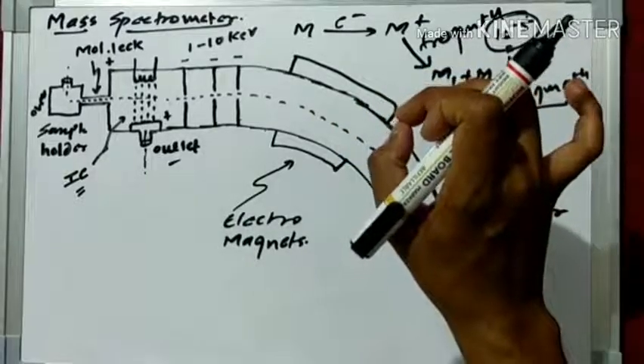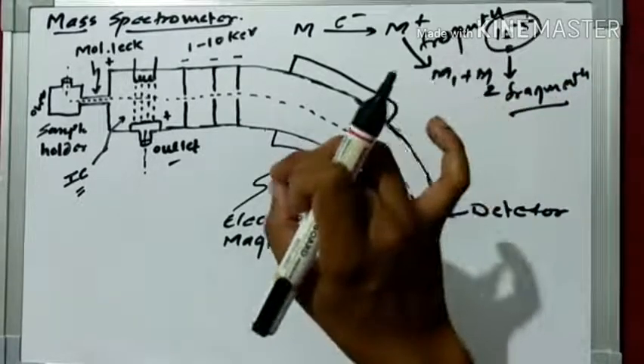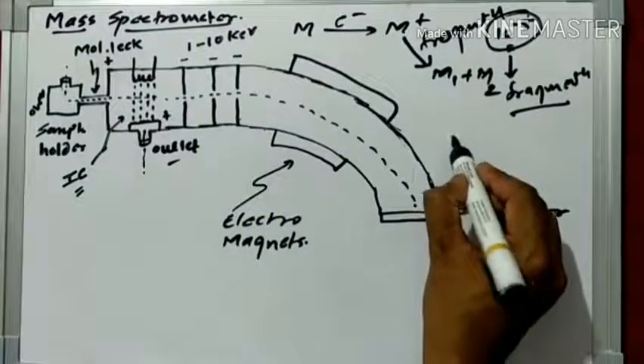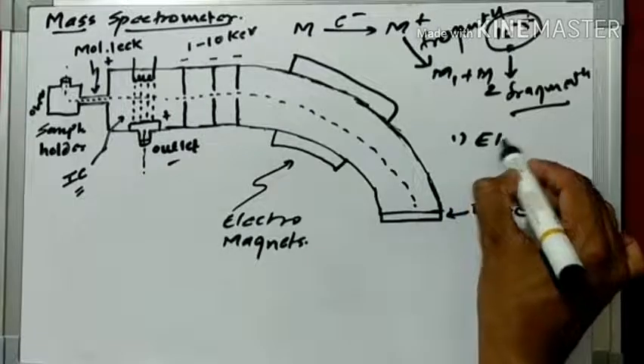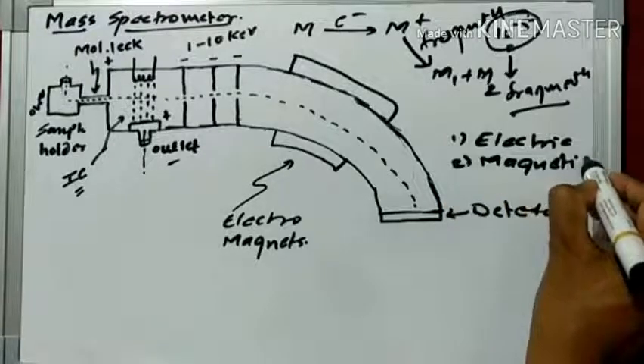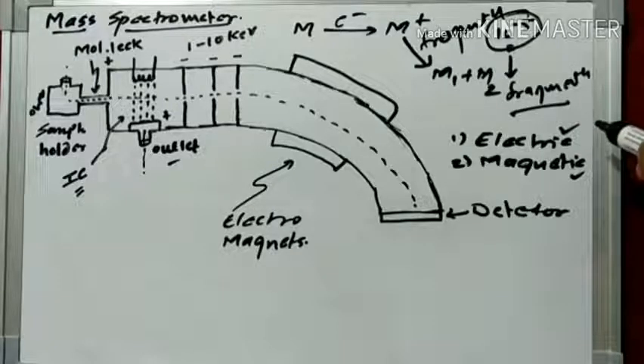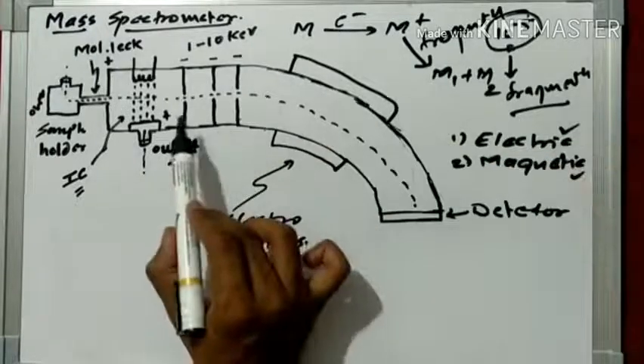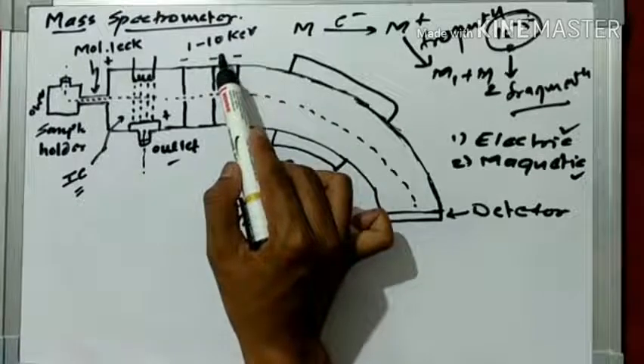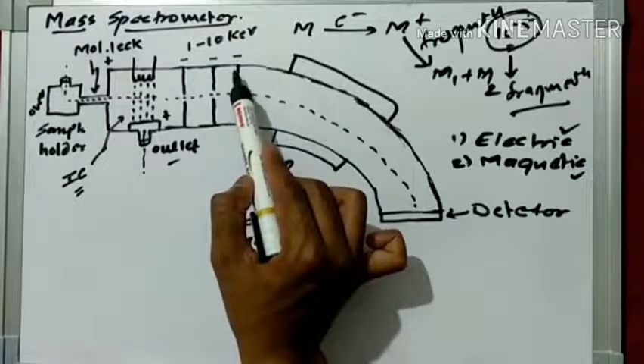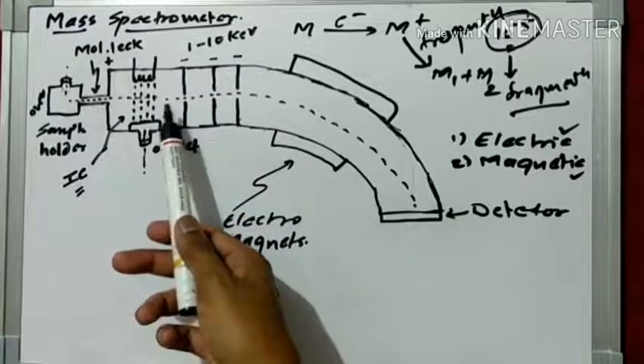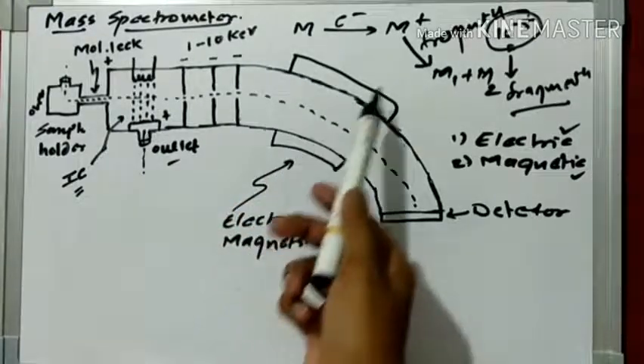In a mass spectrometer, two types of fields are applied. The first is the electric field, and the second is the magnetic field. I will show you where these fields are applied in the mass spectrometer. This electric field is applied using accelerating plates — we apply one to ten kiloelectron volts of potential across these plates. When a positive particle passes through this accelerating plate, these electromagnets provide the magnetic field.